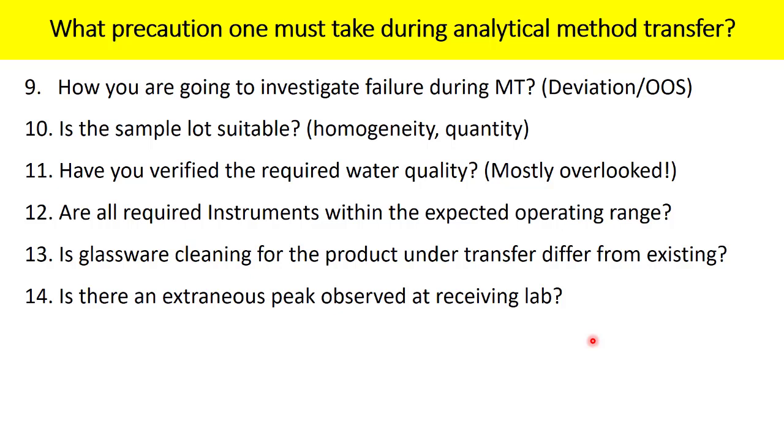Is there an extraneous peak observed at the receiving lab? I am talking about the chromatography technique. Maybe gas chromatography or HPLC. Now in this case extraneous peaks are very important especially during residual solvent or related substances analysis. So have a look in those points. It is not only about comparing the related substances observed at the transferring unit and the receiving unit. But the extraneous peak also needs to be evaluated very critically.